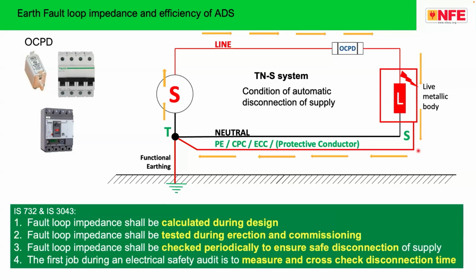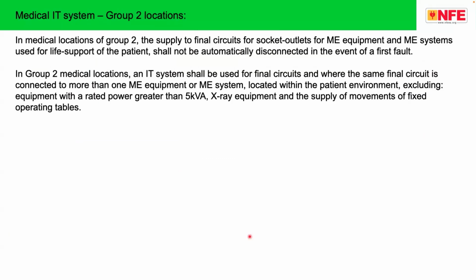The CEA regulation as well as the NEC have emphasized this subject very much. And ideally, in a hospital, fault loop impedance shall be calculated during design, and it has to be tested during erection and verification. This is just to ensure that in case of a problem, your supply is disconnected in order to make the area safe. There is no fire. That is the job.